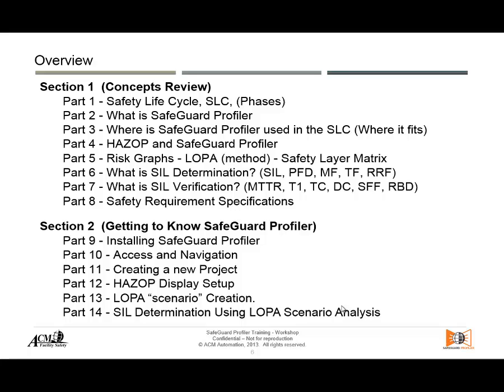What is the relationship between HAZOP and Safeguard Profiler? We will look at what a hazard and operability study is, and how it relates to what Safeguard Profiler can provide. We will cover risk graphs, layer protection analysis methods, and safety layer matrix. All three are methods for SIL determination. Key concepts include: safety integrity level (SIL), probability of failure on demand (PFD), PFD average, mitigated frequency, tolerable frequency, risk reduction factors, and reliability.